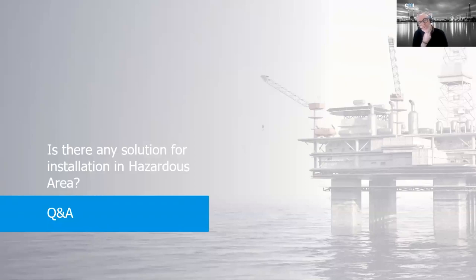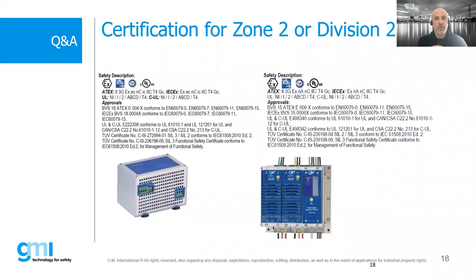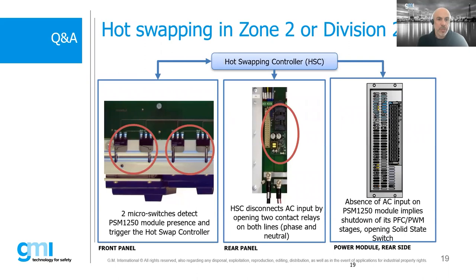And now, what is the solution for installation in hazardous area? Well, for hazardous area, we have a solution with certification for installation in zone 2 or division 2, for Europe and also for America. If you take this rack mounting, there is a special hot swapping feature for disconnecting the unit also in zone 2. So this installation is also for zone 2, and this is also hot swapping for zone 2. There are indeed these micro switches and relays that disconnect the unit from the AC input power in zone 2.